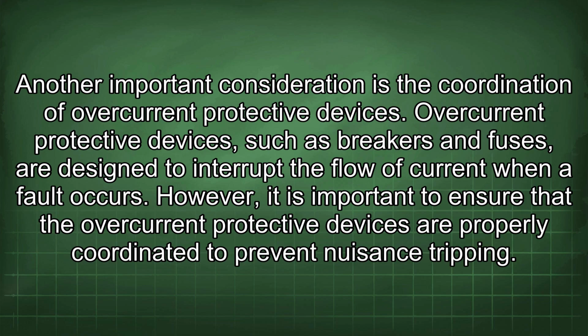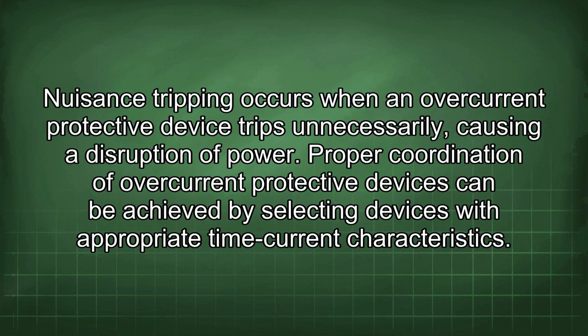Another important consideration is the coordination of overcurrent protective devices. Overcurrent protective devices, such as breakers and fuses, are designed to interrupt the flow of current when a fault occurs. However, it is important to ensure that the overcurrent protective devices are properly coordinated to prevent nuisance tripping. Nuisance tripping occurs when an overcurrent protective device trips unnecessarily, causing a disruption of power. Proper coordination of overcurrent protective devices can be achieved by selecting devices with appropriate time current characteristics.